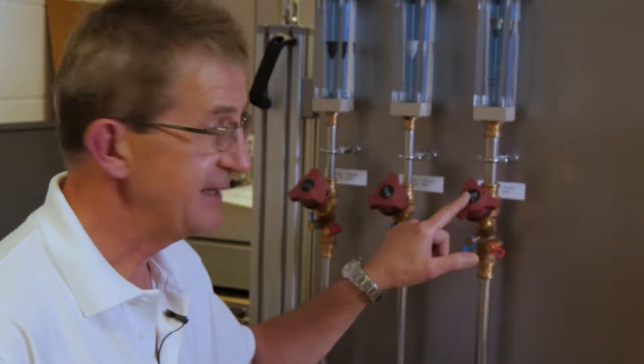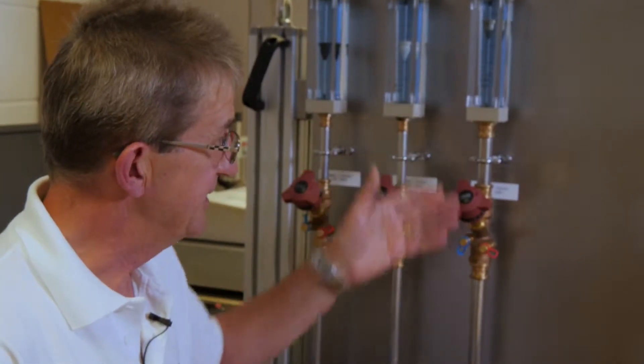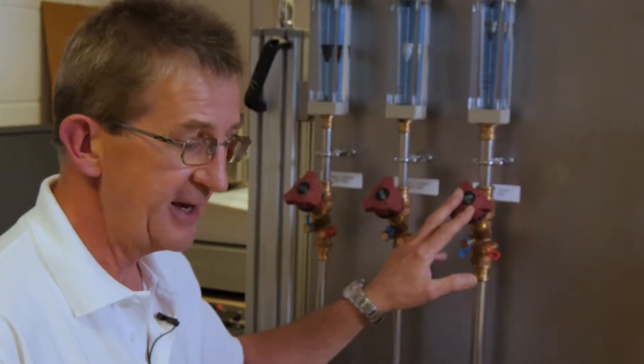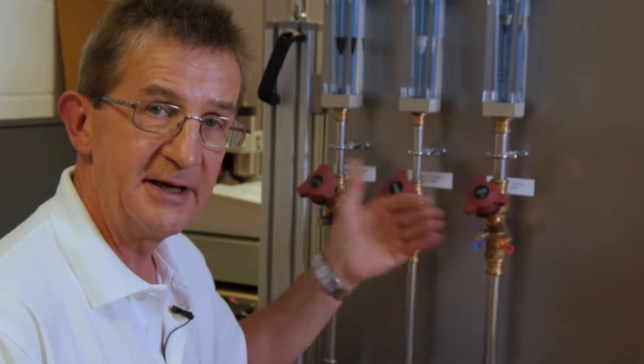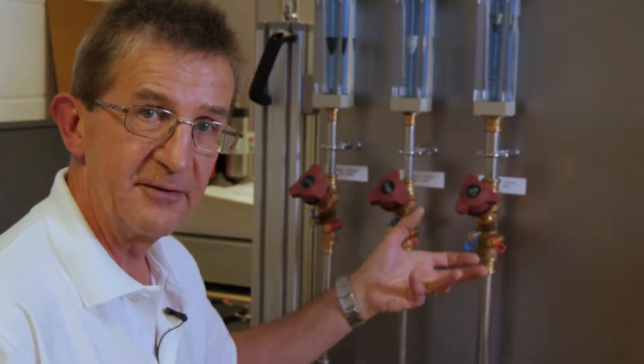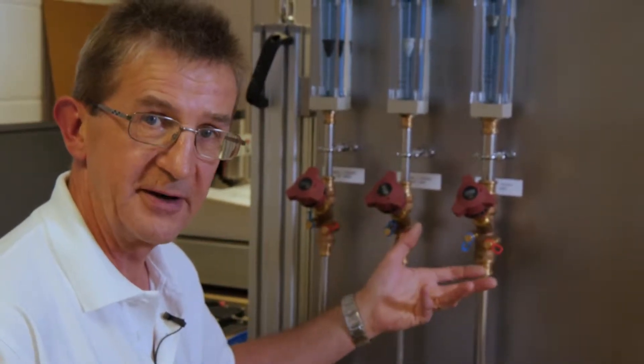Now the PF stands for press fit and this is in a press fit system, so we need to be careful when we're selecting the valve that we don't just choose a standard D931 but this is a D931PF, slightly different flow characteristics, slightly different KVS.